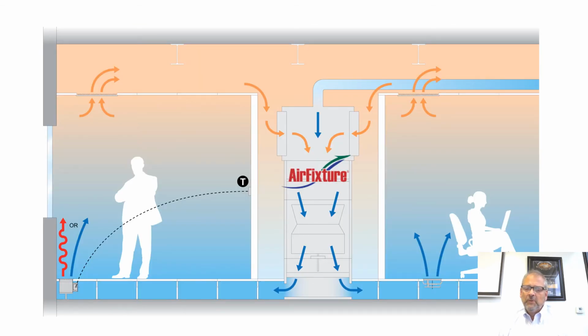Here's what a typical system looks like. This is an AirFixture air handling unit. It's specifically designed to take air and inject it into the floor. A standard air handler makes 55-degree air, and that's too cold for floor dispersement. This unit makes 65-degree air by blending some return air into the cool discharge air, and it's perfectly designed for this type of system.